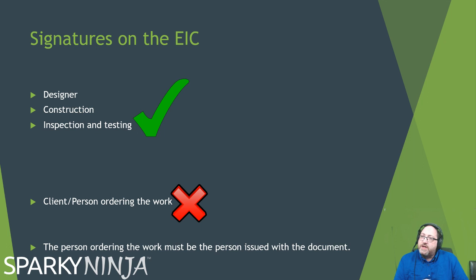Also with these reports, we've got to consider who applies the signature on these documents. This gets challenged a lot. So there's a box for signing the design, the construction, and the inspection and testing. Quite often the answer that's the wrong one is the client or the person ordering the work. They do not sign on these documents, but what might be mentioned as well is they are the ones the documentation is actually issued to. So they're not issued to the designer or the site manager or the head contractor. All certification and reporting must be issued to the person ordering the work.